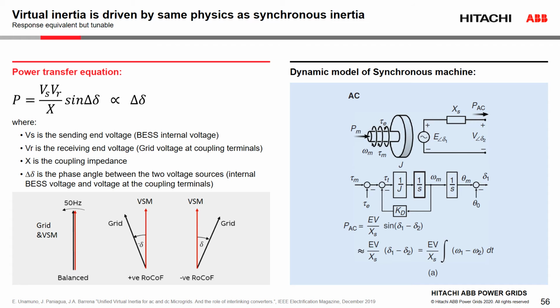In the top left, we have the power transfer equation, which dictates the real power transfer from the converter to the grid. We have the product of the voltages of the grid and the converter divided by a coupling impedance and the sine of the phase angle between the two voltages, the grid and the converter. This is the exact same equation that dictates the inertial response from a synchronous machine, as we see on the right. So when we look at the phasors on the far left, the grid and the virtual synchronous machine are both spinning at 50 Hz.